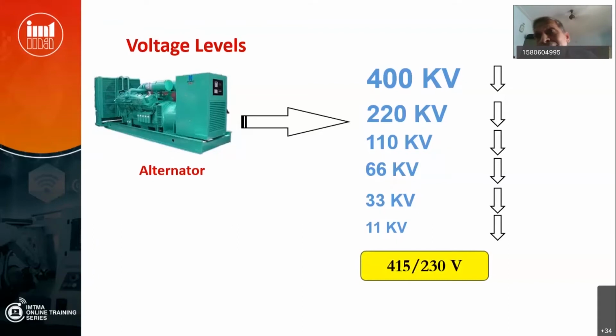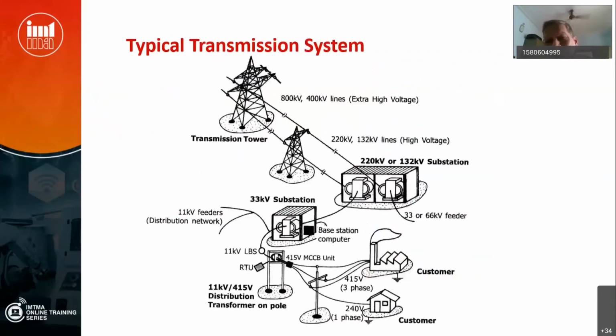So generally, finally, at the user level, at the domestic level, it is maybe a single phase load between phase and neutral, 230 volts, and for three phase loads, LT, that is 415 volts generally. In many of the industries, large industries, we have high voltage equipments also. When I say high voltage, it may be 3.3 kV, 6.6 kV, even 11 kV. Motors in the sugar mills, for example, that churning mill motors may be 6.6 kV rated. Most of the cement mills, in many places in process industries, we find very heavy capacity motors which are supplied with either 3.3, 6.6 or 11 kV. They are high voltage motors. Why we are using high voltage motors, I will explain. Why not only low voltage motors? I will explain when we talk about motors.